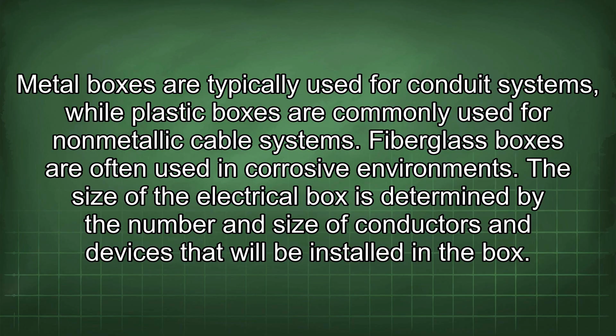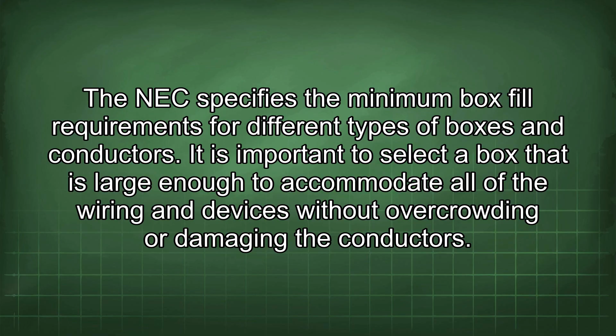The size of the electrical box is determined by the number and size of conductors and devices that will be installed in the box. The NEC specifies the minimum box fill requirements for different types of boxes and conductors. It is important to select a box that is large enough to accommodate all of the wiring and devices without overcrowding or damaging the conductors.